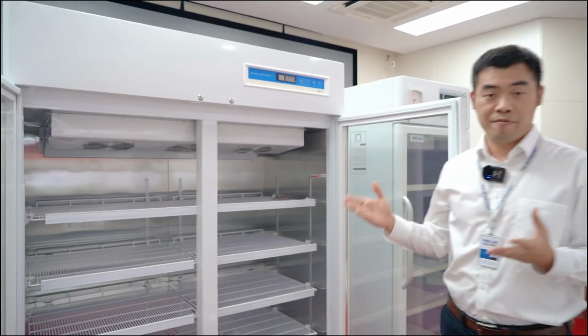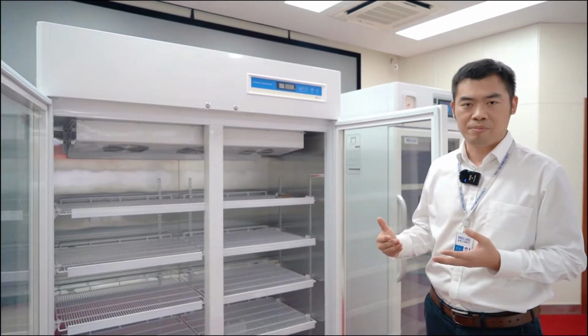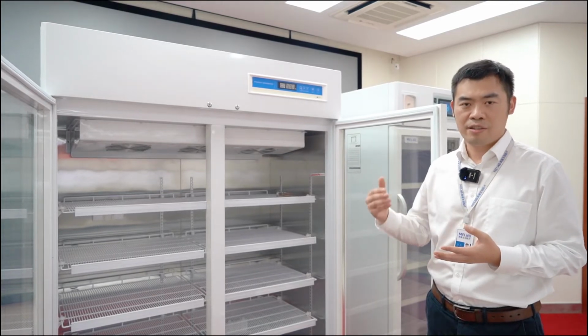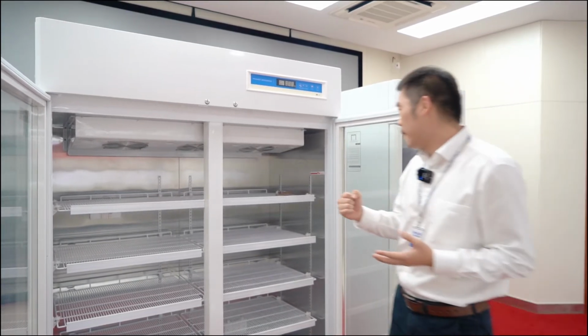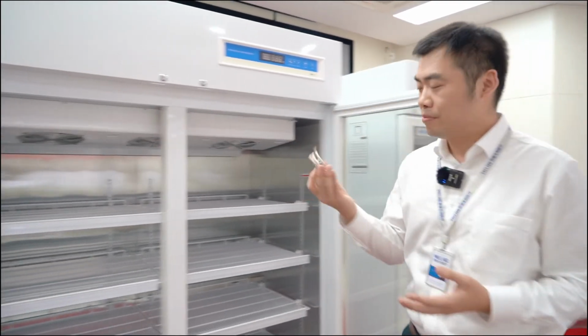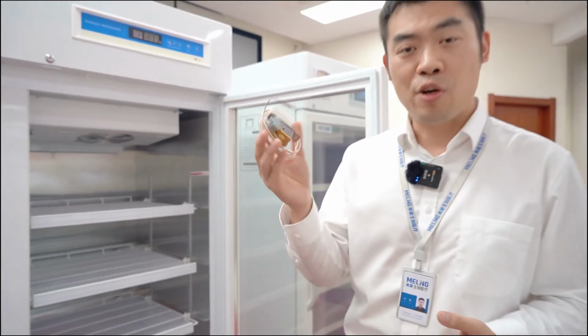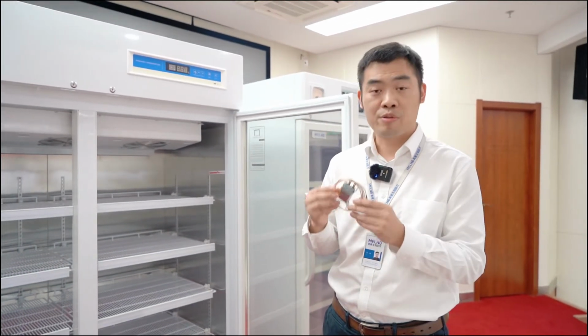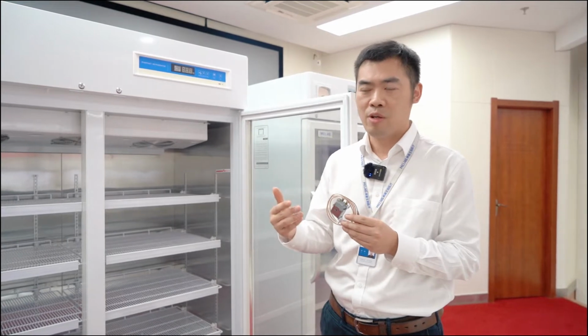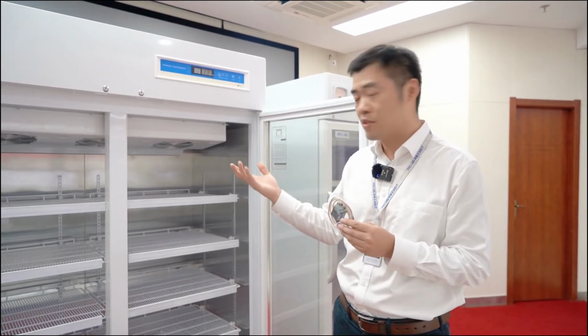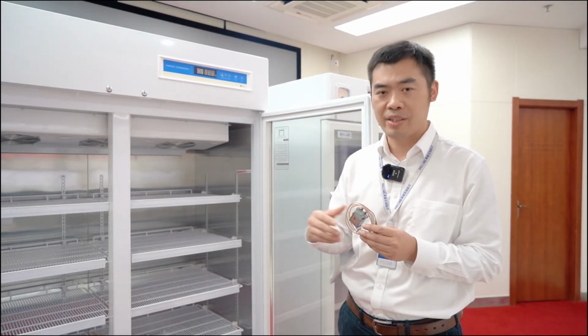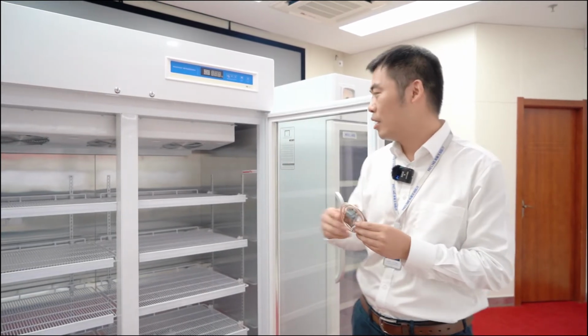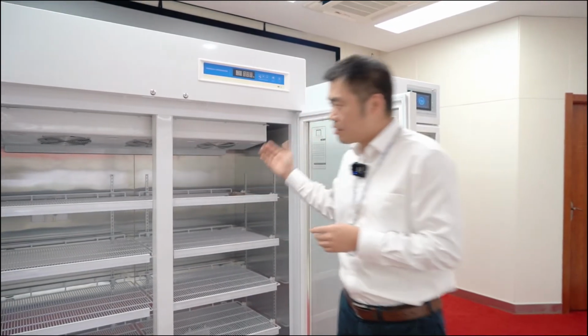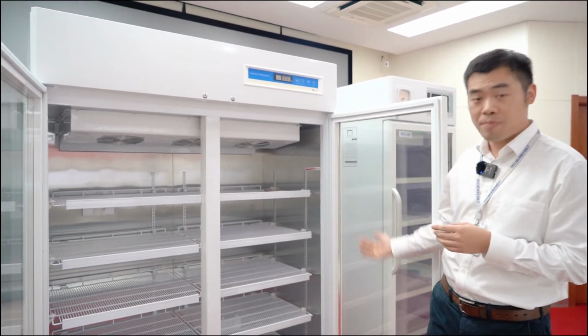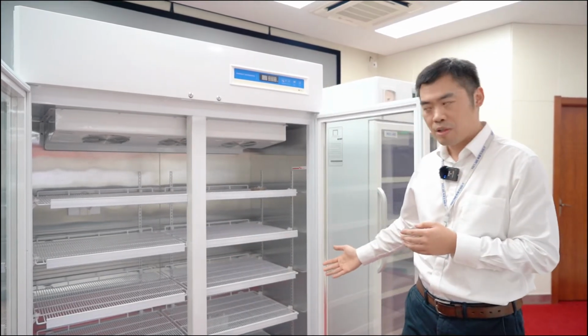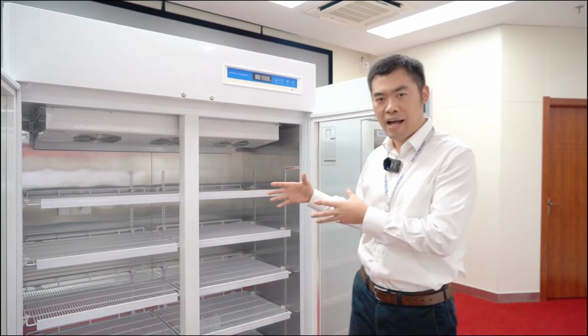We use a fin-type evaporator and a forced air cooling system to maintain excellent uniformity. And you see, this is a mechanical temperature controller, which is programmed to kick in and stop cooling once the temperature inside the cabinet goes below 2 degrees. That's very dangerous to the samples. And the unit is programmed to optimize the airflow so the contents inside do not freeze.